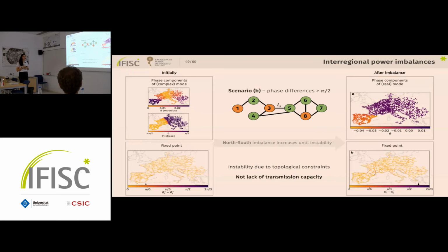This is scenario B that I was explaining before. What happens is that after this line goes above pi/2, its power flow starts to decrease, so the other lines increase their phase difference to compensate and transmit more power between these 2 areas. However, at some point increasing the phase difference no longer leads to more power flowing through these lines, and that is when the instability emerges. Because of that, we can say the instability is not really due to a lack of transmission capacity, since the lines are not fully loaded, but due to topological constraints.